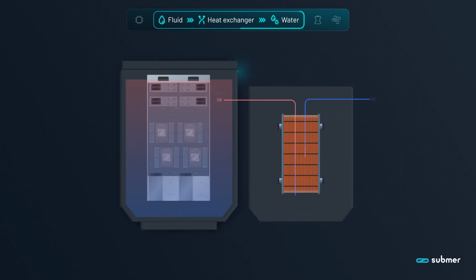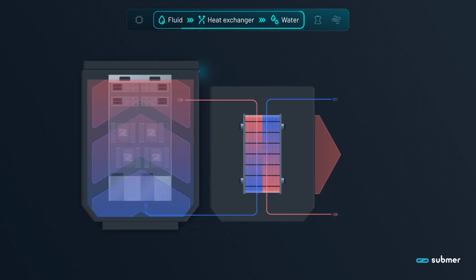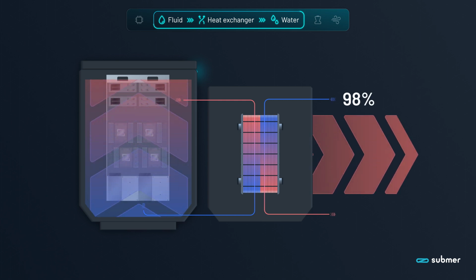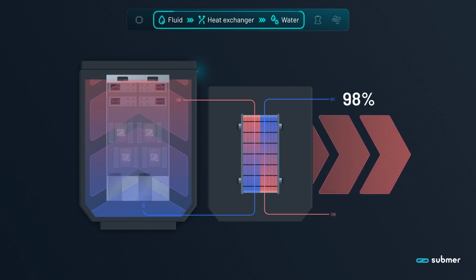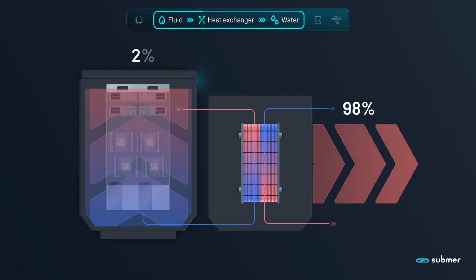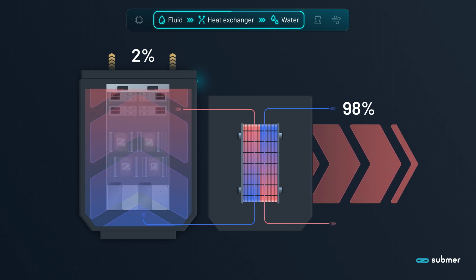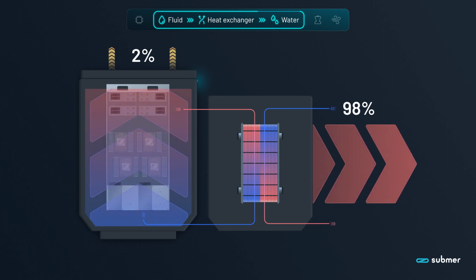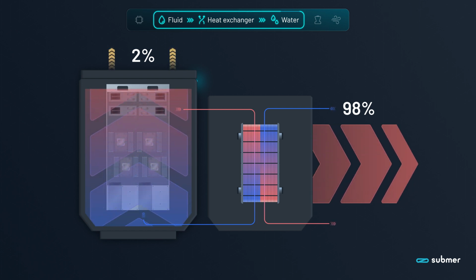The hot immersion fluid is transported directly to the heat exchanger in the CDU, where it transfers 98% of the heat to the secondary fluid. The remaining 2%, originating from the pods and piping, is effectively managed by simple air handling units.